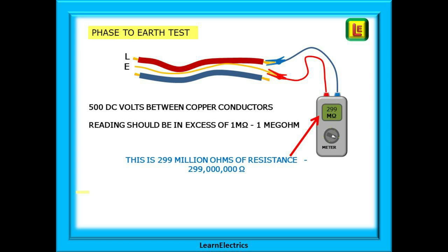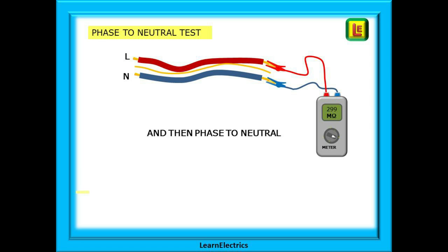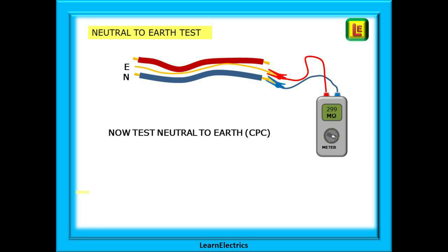Readings for a good test — a pass — are in excess of one megaohm of resistance, one million ohms. Typically most test meters will show 199 megaohms or 299 megaohms, the meter maximum, for new installations. Our first test will be between the phase and earth conductors. Phase or line are both acceptable names, as is earth or CPC for the circuit protective conductor. Then we will test between phase and neutral, and finally between neutral and earth or CPC as we should really call it.